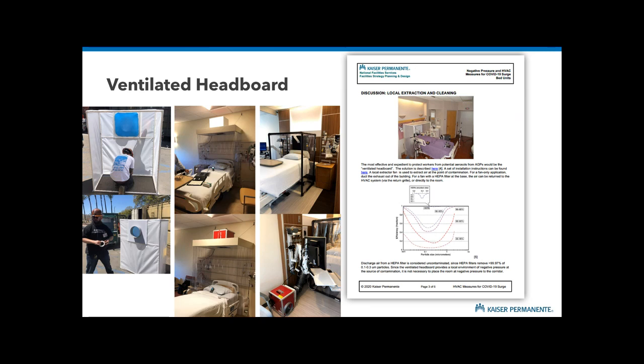If you haven't seen this, you type ventilated headboard into Google and it pops right up. There are do-it-yourself plans right on the website. You can deploy this with zero modifications to the base building system. You take that exhaust from the ventilated headboard, pass it through a HEPA filter and put it right back in the room. You can duct it out in the hallway if you really want to do that, but you can just discharge it right in the room. So compared to some of the very intrusive and frankly very ugly things we saw people doing early on, this really is the best idea.